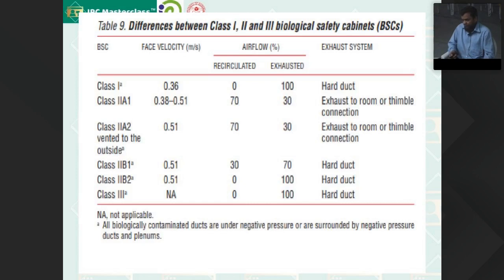Class 2 B1, if you see here, it is the opposite of this. Recirculation is only 30%. 70% is exhausted through the hard duct. It passes through the HEPA filters. Class B2, again, the air is almost the same. There is no recirculation at all. If you see the recirculation, it is 0. Most of the air is exhausted, 100% it is exhausted. And class 2 type B2, again 100% exhausted. So this is how the different biosafety cabinets differ in the biosafety classes: class 1, class 2, A1, A2, B1, B2, and class 3 cabinets.